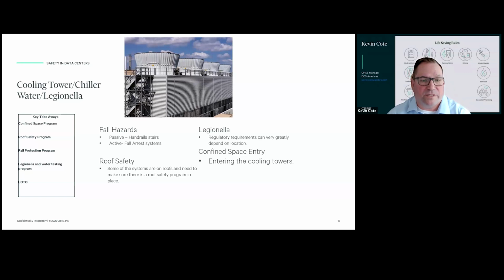Another concern is Legionella and water management. You need a water management program, contractor or on-site, where you're doing testing. This really depends on where you're located—each state, city, or county may have its own Legionella program. Some states require nothing, others require an annual test, and some cities or counties are more stringent and require monthly testing. New York is very strict on Legionella, and New Jersey is following New York's lead, so if you're in New Jersey, look for the Legionella rule to change within the next couple months.